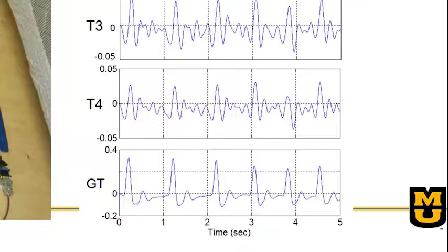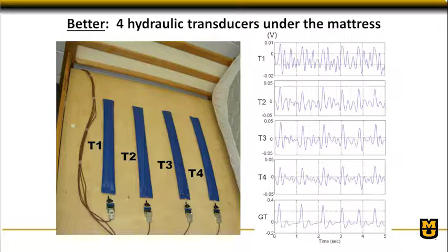And so these represent each of the pulse rates, the heartbeats. And then you can see what these filtered signals look like. Once you filter out the respiration, you can see what the 4 transducers look like. Now, depending on which transducer somebody's actually lying on, you'll have either a clearer signal or a signal that looks a little bit noisier. But we've now figured out how to identify which is the best transducer signal to use for a particular 15-second segment.